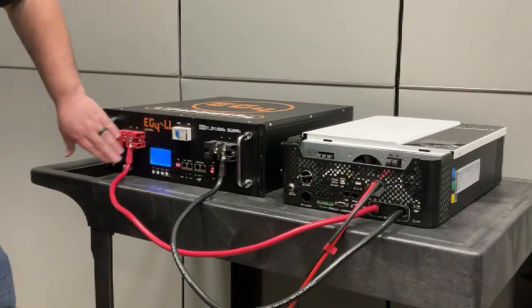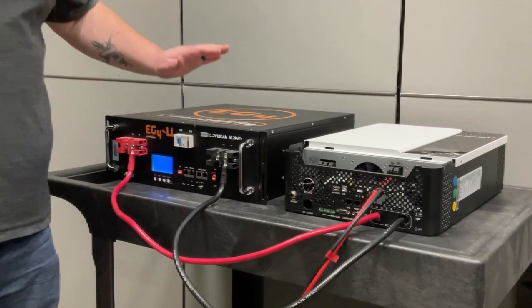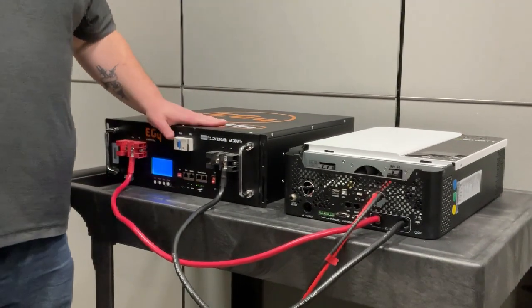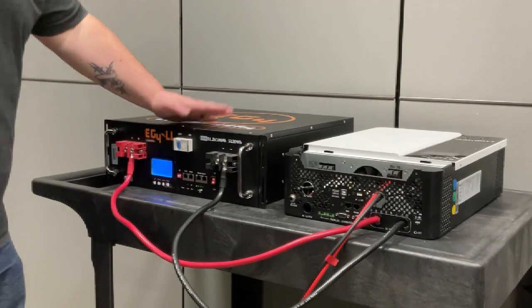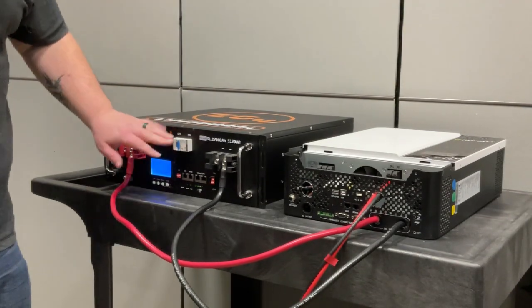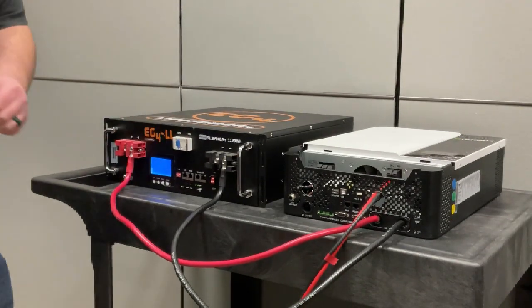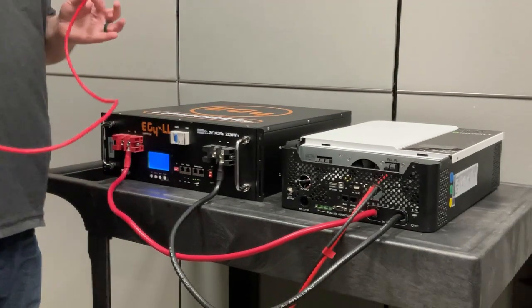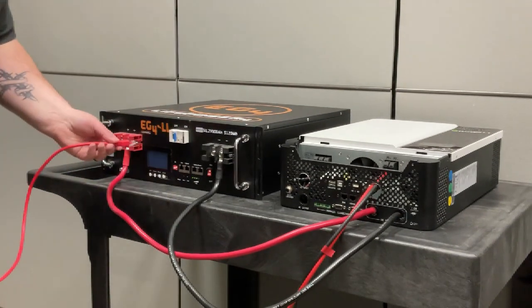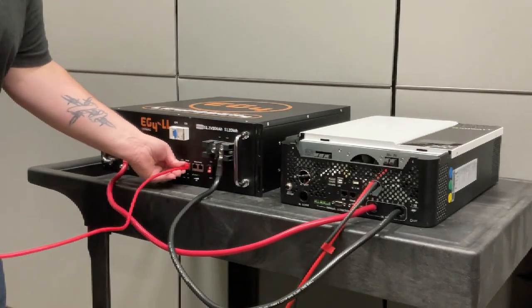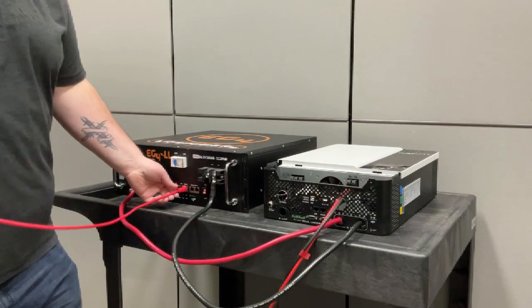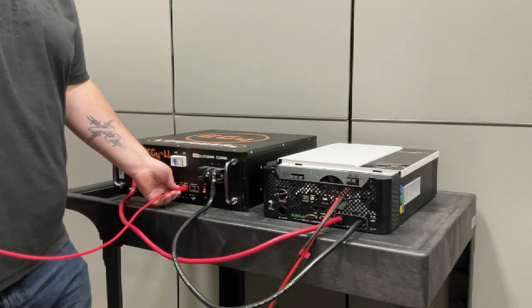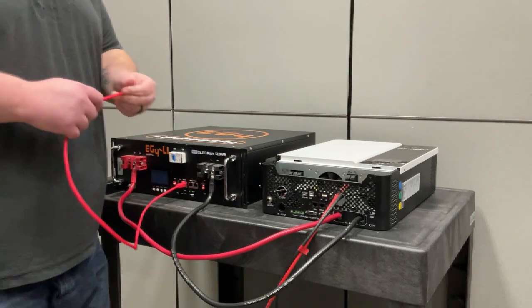So now at this point, you have got your battery dip switch in the master communications configuration. Your battery is on. You'll take your communications cable and you're going to come out of the RS-485 port in the front of the battery.